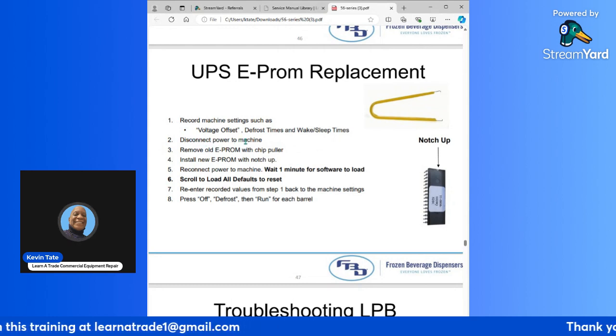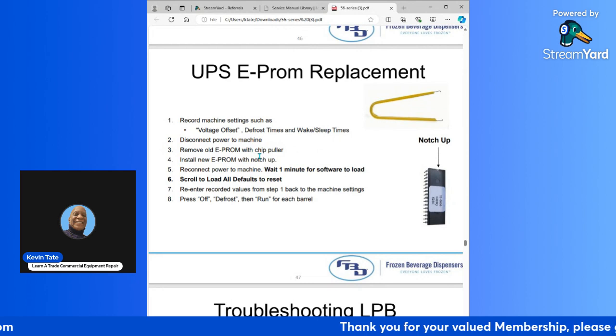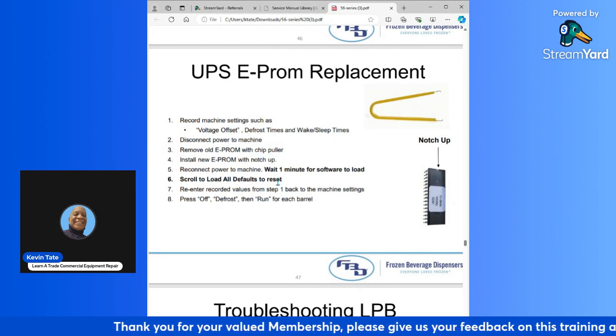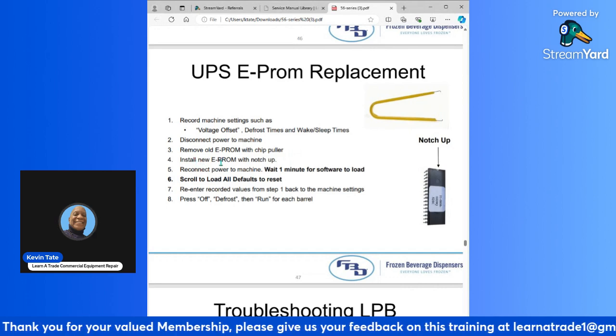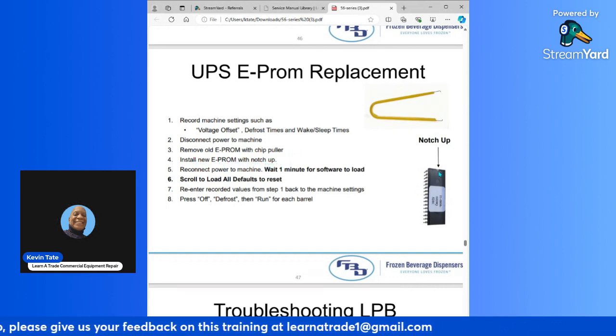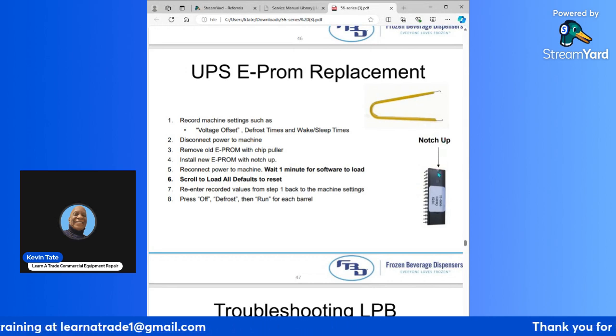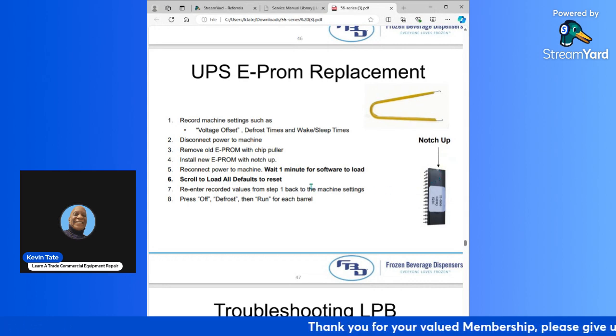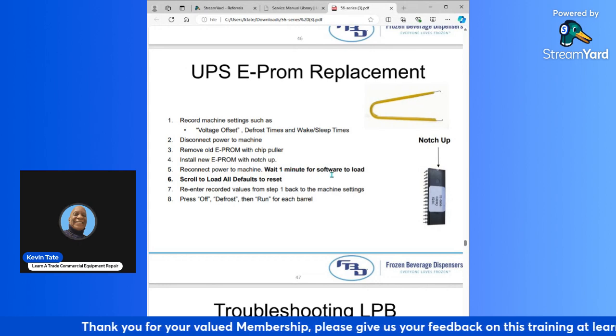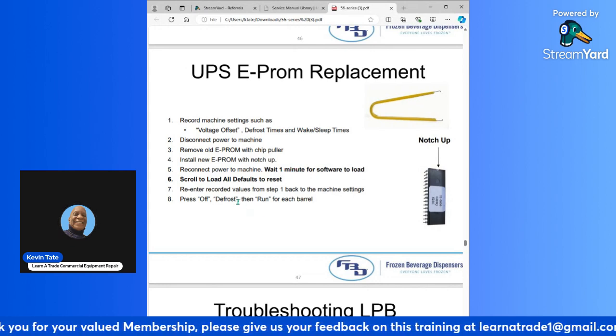Next, you would disconnect power to the machine, remove the old EEPROM chip with the chip puller. That's with this tool right here. Install the new EEPROM chip with the notch up. The notch is right here. This little notch right there up top. That's going to be facing up always. Reconnect power to the machine. Wait 1 minute for software to load.